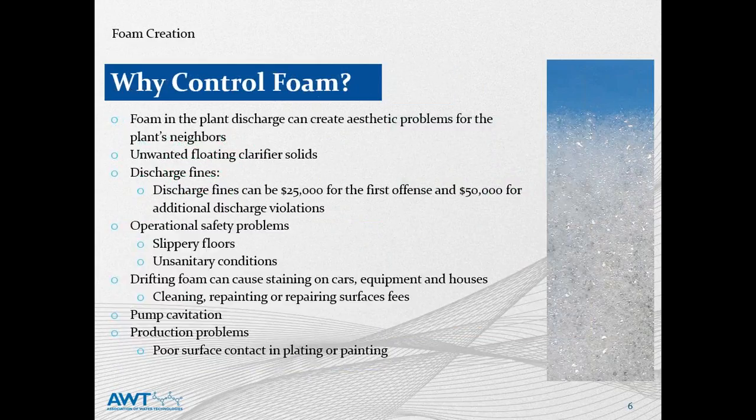So why should we control foam? What is the reason foam causes problems in our industry? Foam can be an aesthetic problem to neighbors and surrounding accounts — nobody really wants to see foam in their backyard or on their streets. Unwanted foam in clarifiers can actually cause solids to float out of clarifier systems, causing you to miss discharge limits on suspended solids. In Pennsylvania, an illegal discharge of foam can range around a $25,000 fine, and on your second discharge, about $50,000. So there can be significant fines for discharging foam.